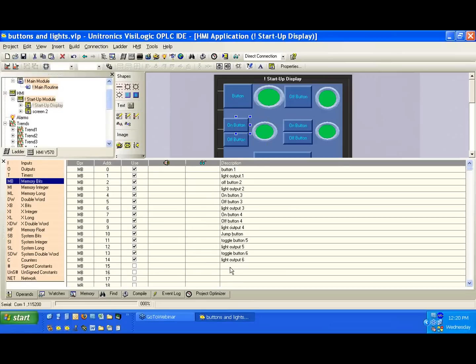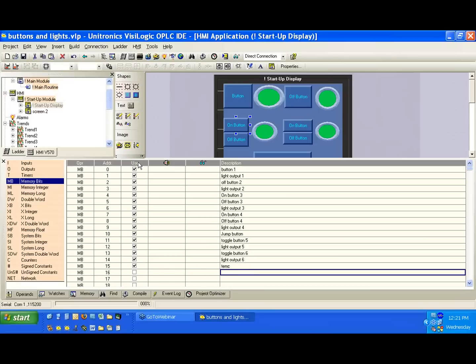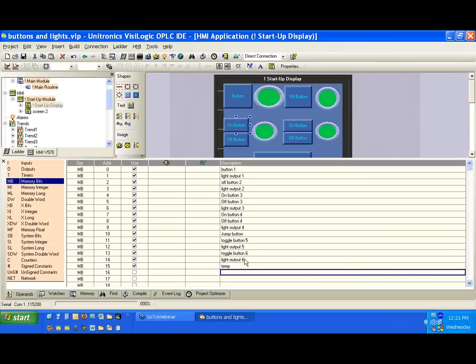Well, first you link it to something, or we can give it a description. So if we wanted to take memory bit 15 out of the system, we can just type temp here, hit enter, and we notice that now memory bit 15 is out. So if we want to reserve a vector or a list of memory bits in a row, we can use this to take it out of use. And it's important to understand that when we get the next unused, we don't want to accidentally grab something that is in use or we intend to use in the system. So if we need memory bit 14, 15, and 16 in use in the system, we should plan it out and give them a quick description. Really anything in that field will take it out of use.